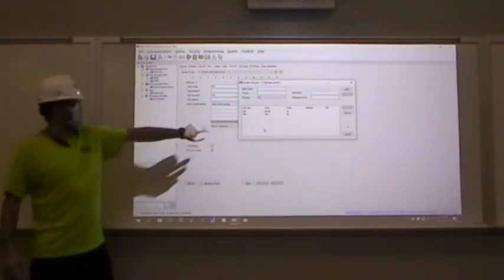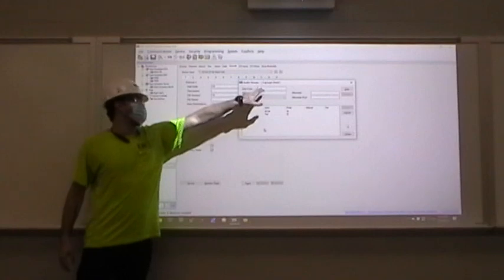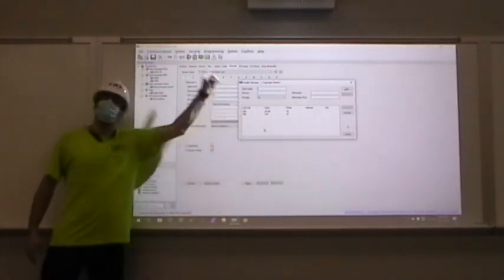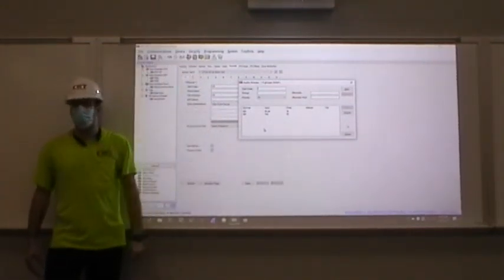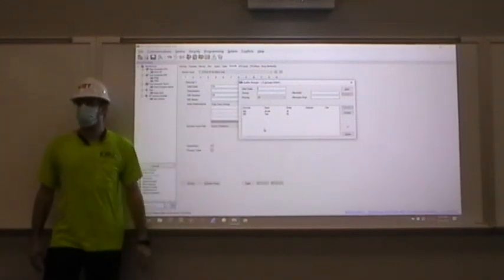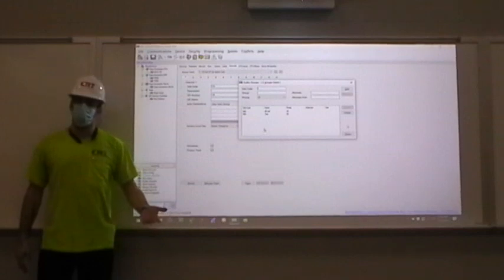Here's where you set up an audio group. Right now I have your all call in there, and I've got a test group that I was planning. I'll probably take that out before we're done. But you can build one by putting in the dial code, naming it, and then setting the priority. A lower number is a higher priority, so that actually goes from 1 to 100. It defaults at 10, and I like to leave that there for the all call. There are other messages that come in at like a 40 default. So if a bell is running and you make an all call, it'll override that bell.